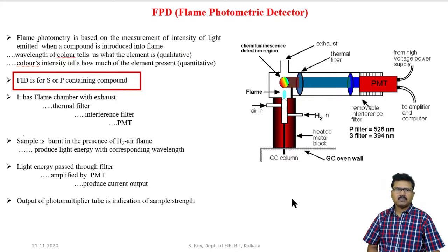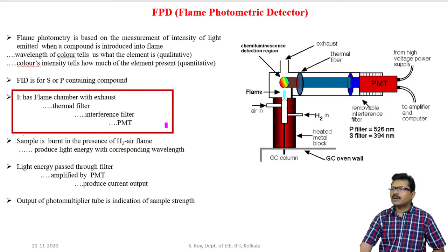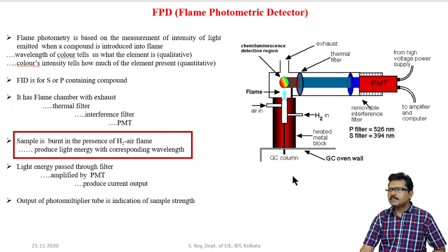Determination of sulfur and phosphorus compounds is the job of the flame photometric detector. As per the construction, it has a flame chamber with a heated block, along with a thermal filter and interference filter, and also a photomultiplier tube. Sample from the column is introduced through a metal heated block. Air and hydrogen mixture produces the flame. When the sample is introduced through this block and contacts the flame, it produces light with a specific wavelength. The sample is burned in the presence of hydrogen-air flame — hydrogen acts as fuel and air as oxidant. This burning effect produces light energy with a corresponding wavelength.